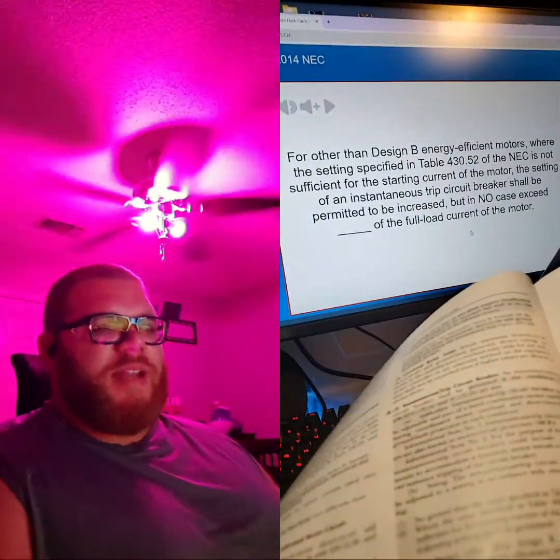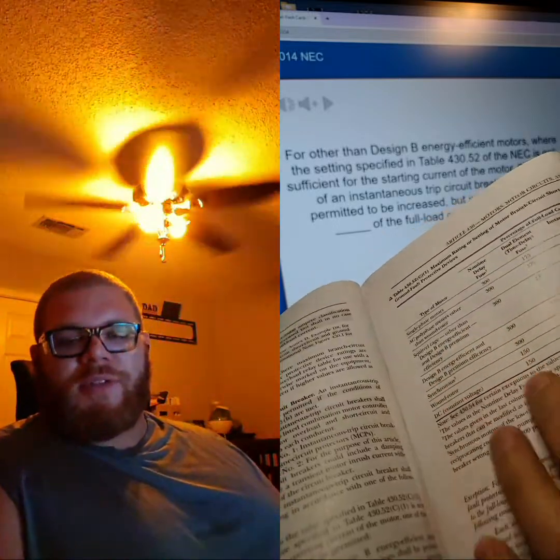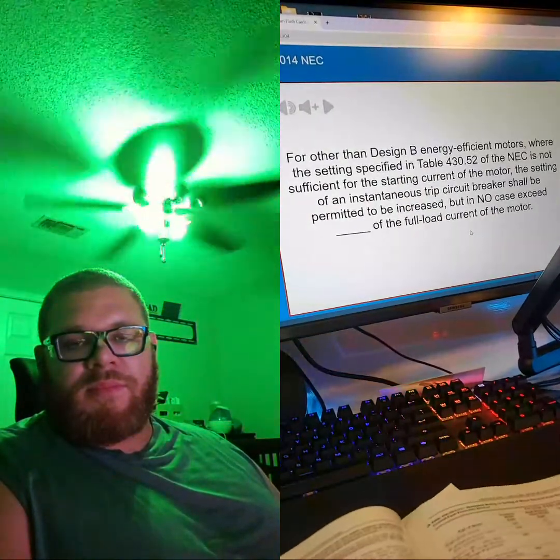Yeah, but it is instantaneous trip. That's how instantaneous trip settings are. It's mainly for design B and design B premium efficiency motors, other than ground faults. I was thinking it was 300%, but I think that's a regular breaker.